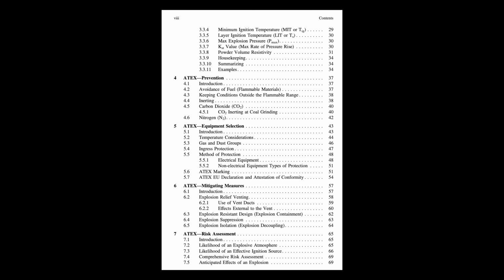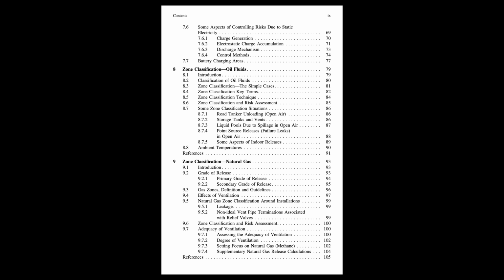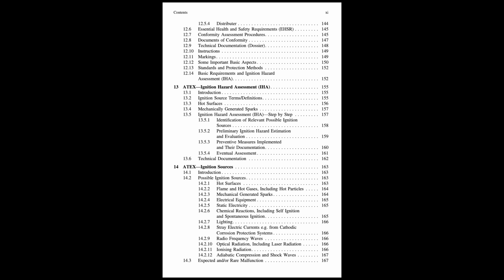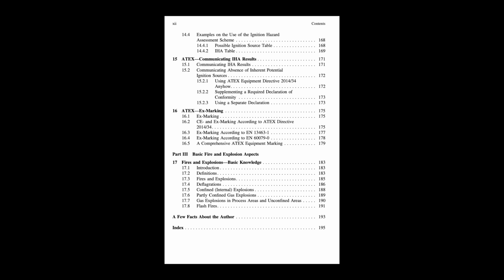Exactly. Poor housekeeping, allowing thick dust layers to accumulate, significantly increases the extent and severity of Zone 22 and potentially Zone 21. The way work is done also matters. Emptying bags openly creates more dust cloud risk, and thus larger zones, than using contained transfer systems. So operator practices and cleaning regimes are part of the zoning assessment for dust. Definitely. And while the dust properties like MIE, MIT, LIT, and KSt don't directly define the zone boundary, they are critical for the risk assessment within that zone and for selecting equipment with appropriate surface temperature limits, considering both cloud MIT and layer LIT with safety margins.